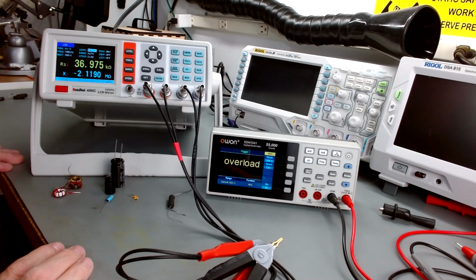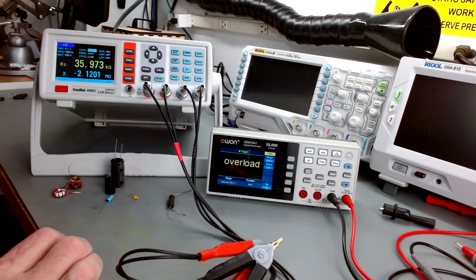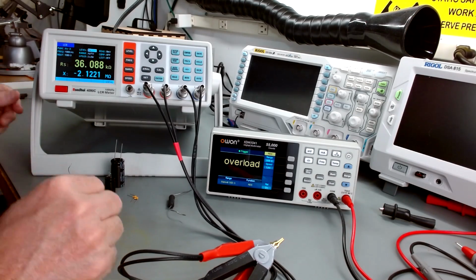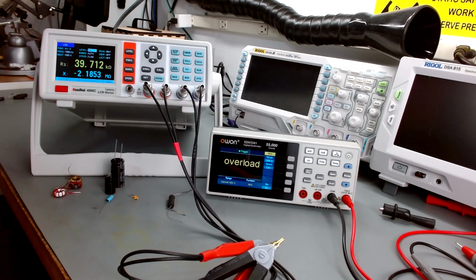Now imagine doing that with a multimeter, where the leads are single conductors, so you have to put the current through the same leads used for sensing. The resistance in those leads creates a voltage drop, and the more current that runs through, the more error gets created in your measurement. At low resistance, with enough current pushed through, you see all kinds of error pile up. You cannot measure 1% resistors very well with a digital multimeter if they're 1 ohm or under.